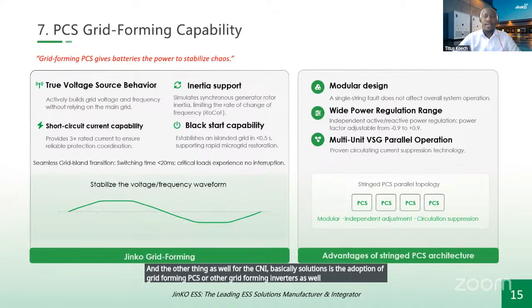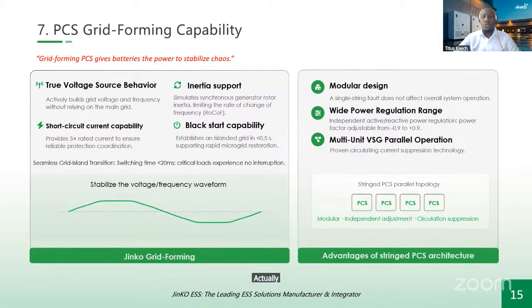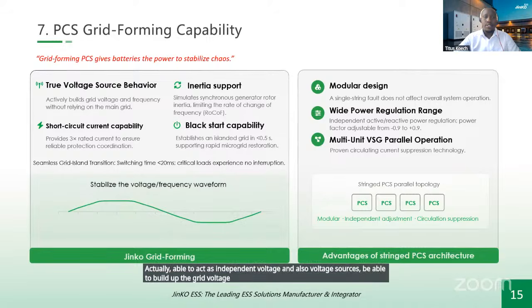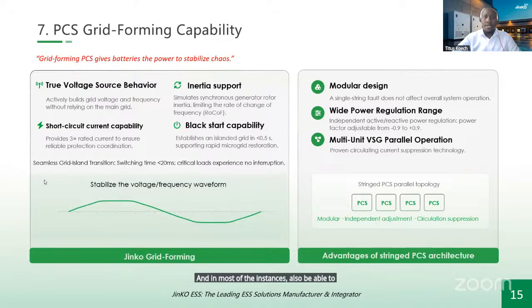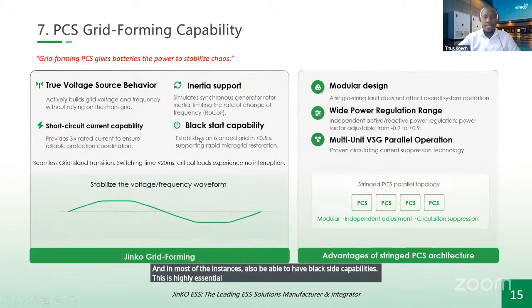Ideally, having these grid-forming inverters which are able to form the grid, act as independent voltage sources, build up the grid voltage and frequency, provide inertial support, and in most instances also have black start capabilities. This is highly essential, especially in regions with very weak utility grids, so ideally we can have this black starting capability.